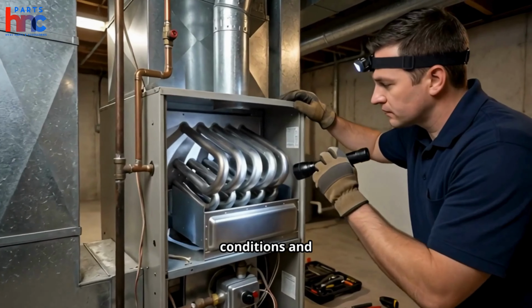After installation, perform critical tests. Verify safety switches work. Use a combustion analyzer to confirm zero carbon monoxide leaks. Ensure proper ignition and efficient cycling, and check for even heat distribution with good airflow.